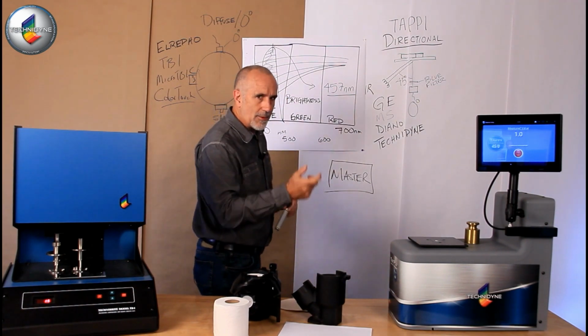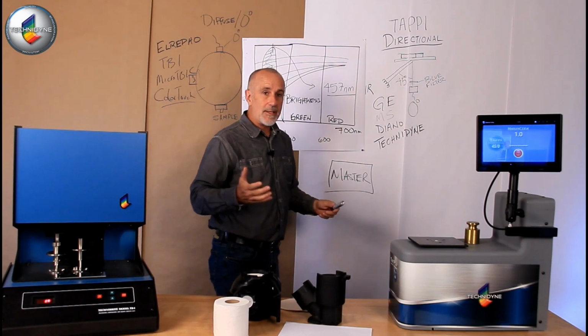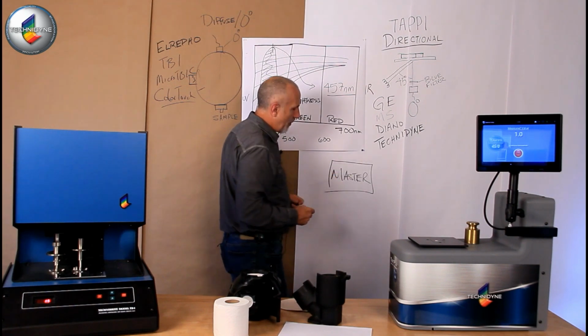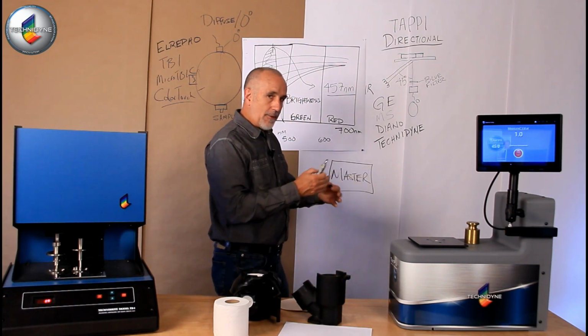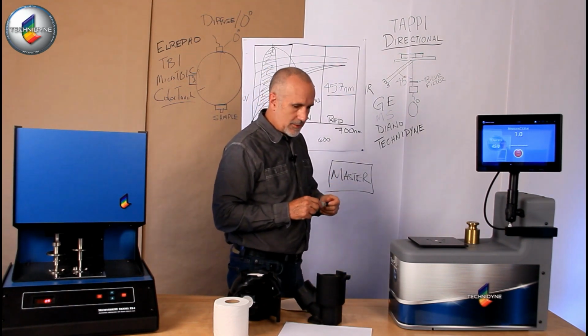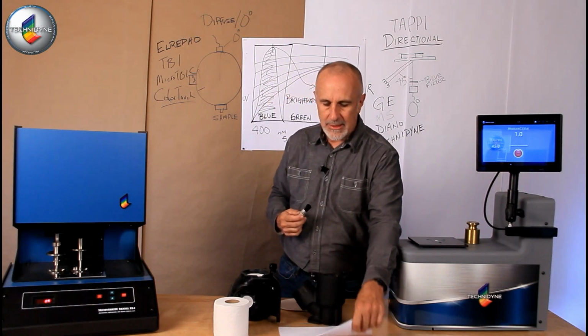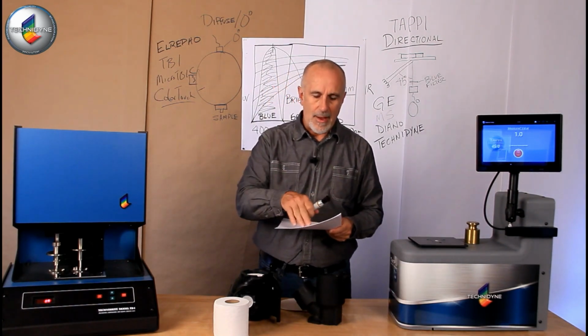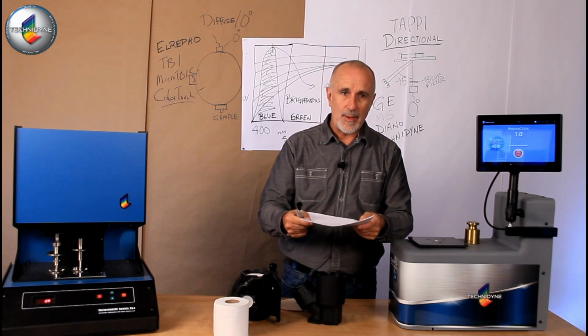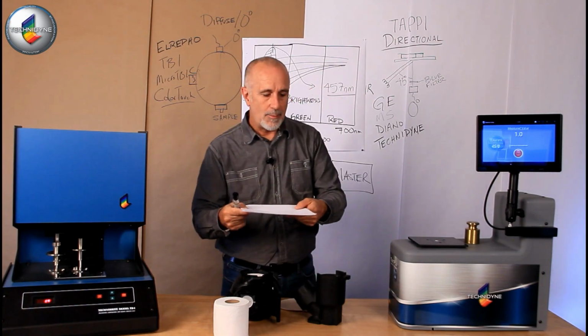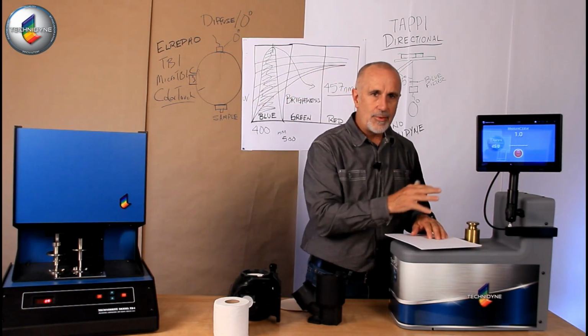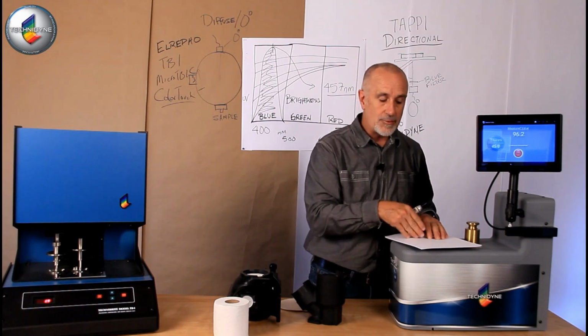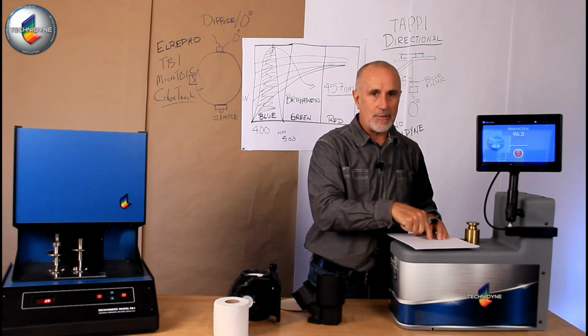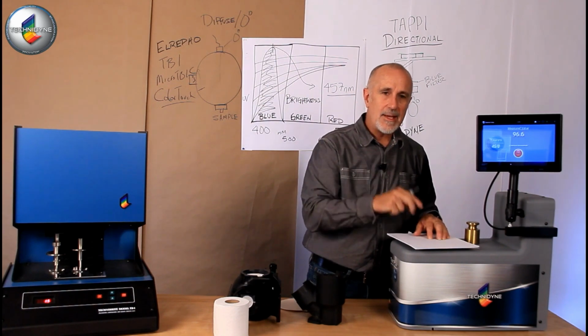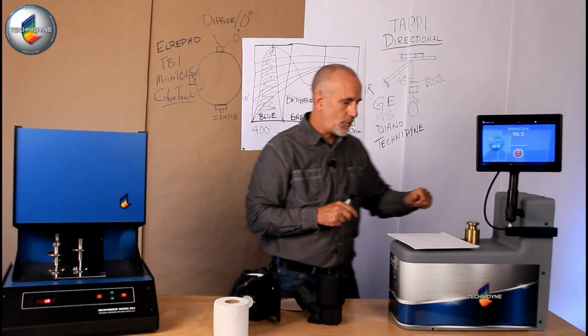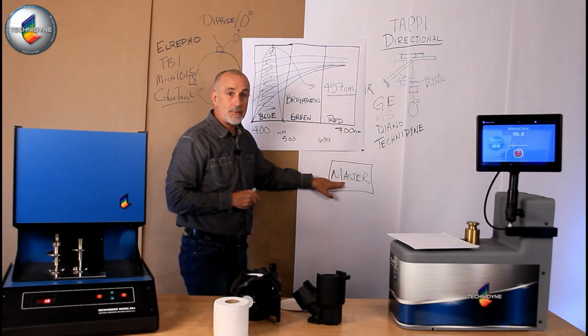So these paper standards are then evaluated on the master instrument. And then the value, let's say for this sample, reads 93. So that value is recorded as 93 for that sample. Then I take that standard and bring it to my instrument, go through the calibration sequence on that instrument, and say read 93 for this sample. What that does is force this instrument back to agreement with the master instrument.